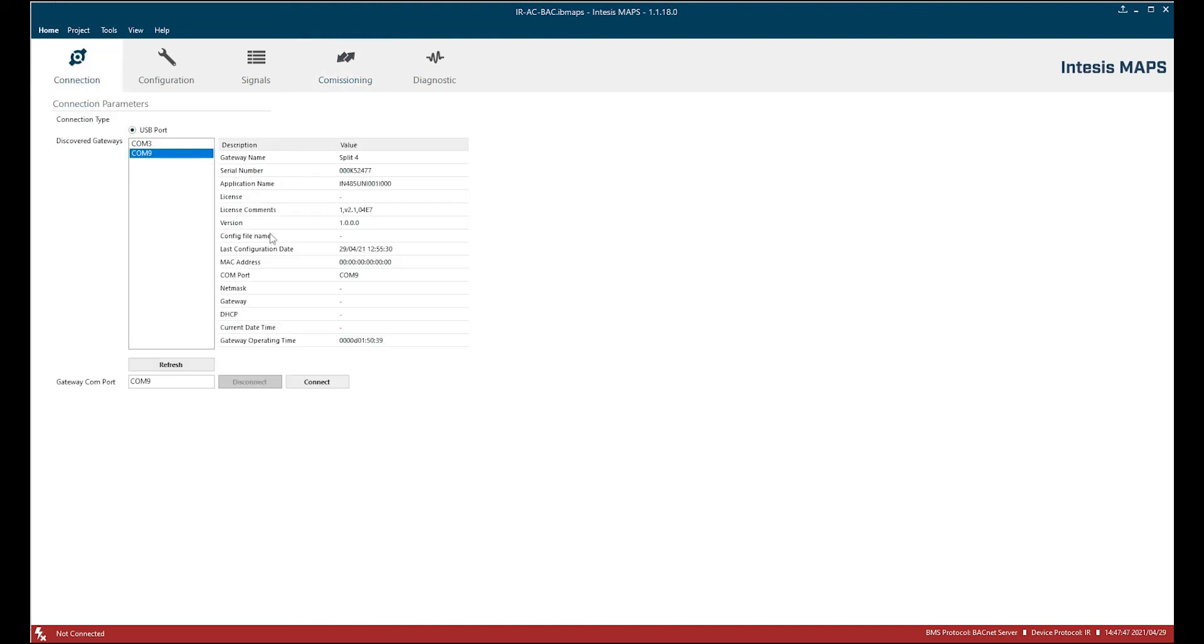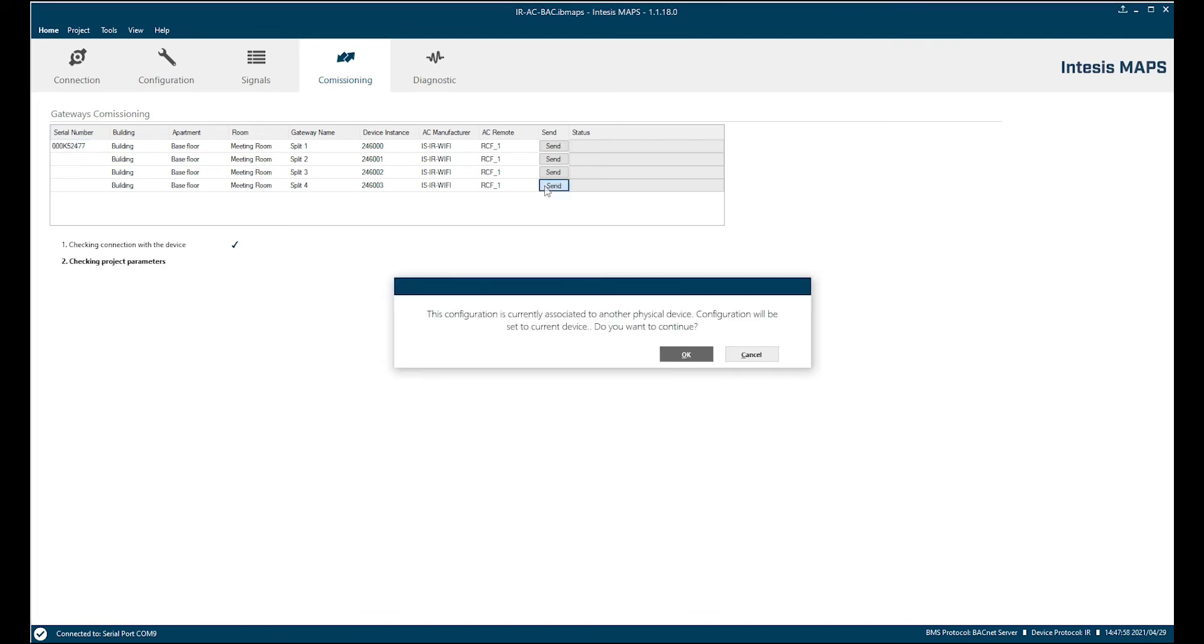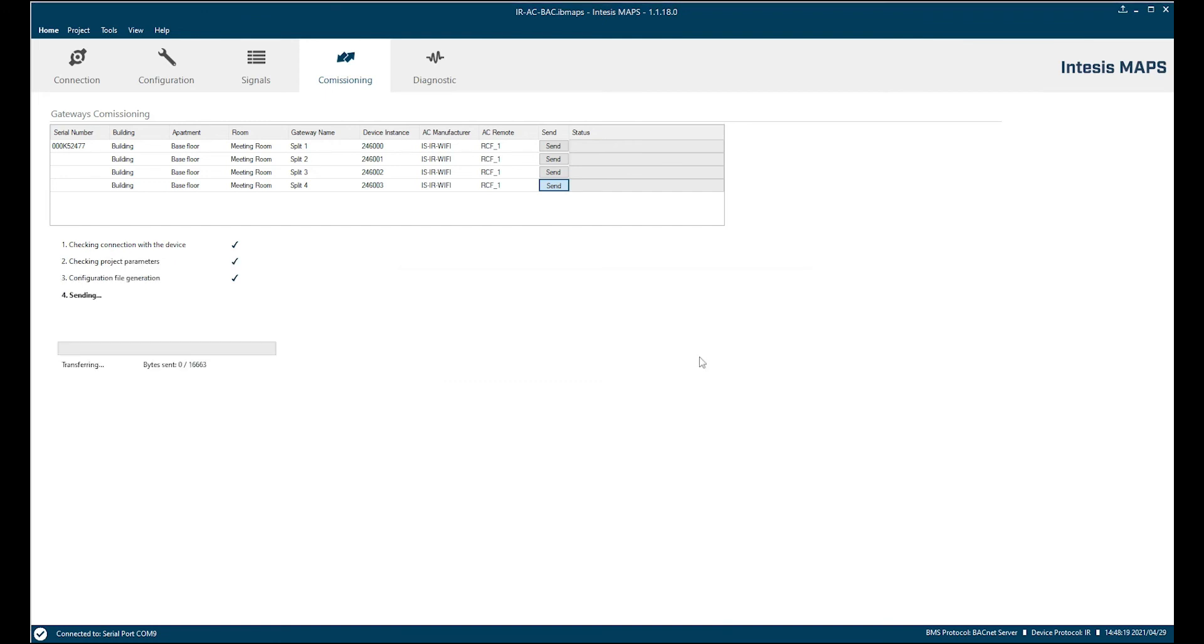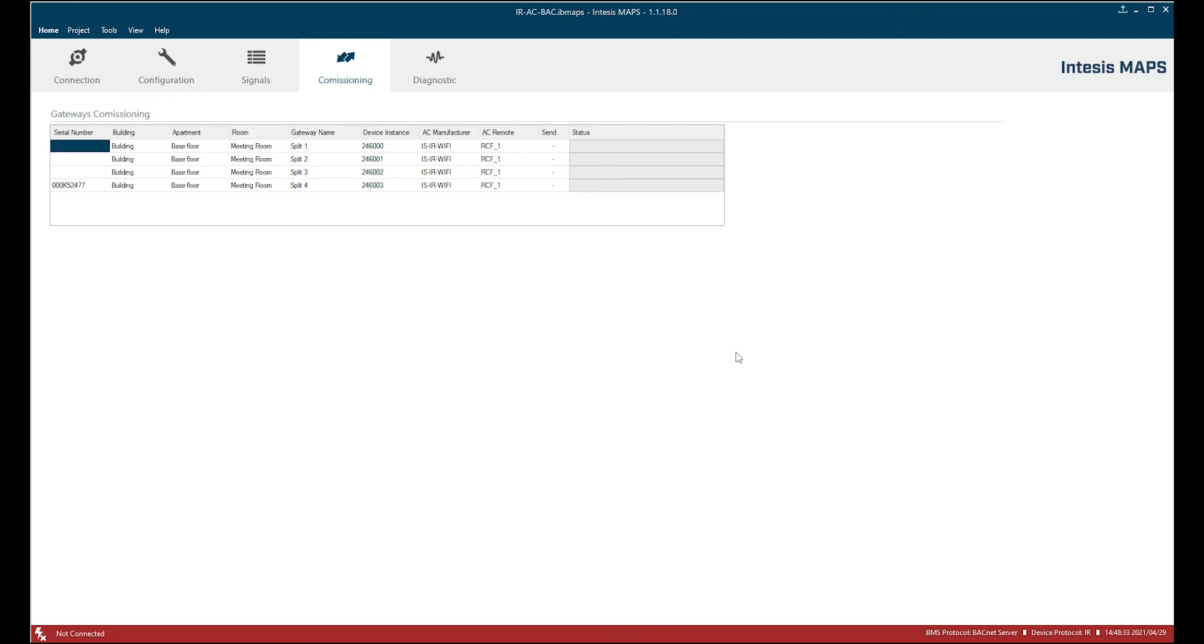I'm going to reconnect the same device and I'm going to say okay, let's send the configuration of split 4 to this device. So a notification appears and it asks me if I want to override this configuration and that this configuration is associated to another physical device. Okay, I'm going to override it. It downloads. It's not going to ask me again about the project saving because it's already saved. And okay, now the download is completed. And you see that the serial number now changed from the split 1 device to the split 4 device.